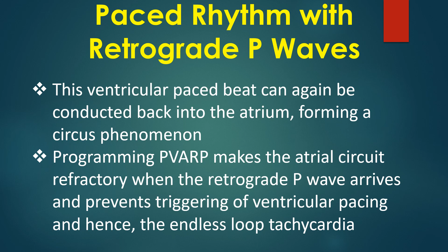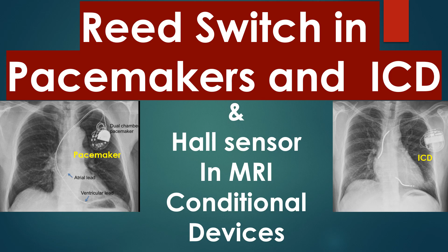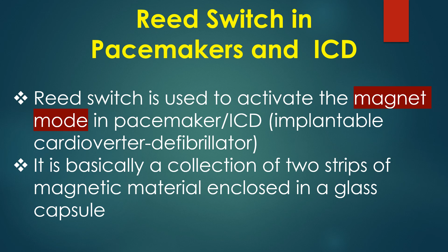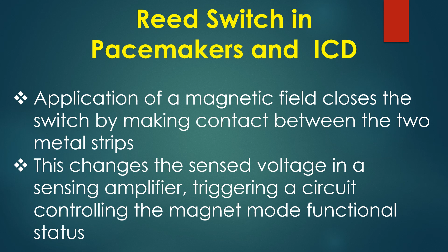This discussion is on reed switch in pacemakers and implantable cardioverter defibrillators. Includes a mention on its replacement by Hall sensor in MRI conditional devices. Reed switch is used to activate the magnet mode in pacemaker or implantable cardioverter defibrillator. It is basically a collection of two strips of magnetic material enclosed in a glass capsule. Application of a magnetic field closes the reed switch by making contact between two metal strips. This changes the sensed voltage in a sensing amplifier, triggering a circuit controlling the magnet mode functional status.